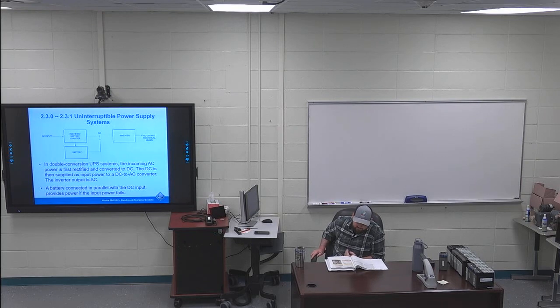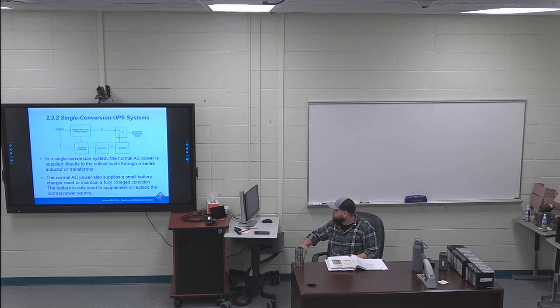The next sentence is a separate highlight. In low power UPS applications, 0.1 kilovolt amps to 20 kVA, the double conversion UPS can have some of the following disadvantages. I just have the lower efficiency. So at these levels, these UPS systems can have a lower efficiency. Going on to 232, the single conversion UPS system, I've got the second sentence highlighted. The normal AC power is supplied directly to the critical loads through a series inductor or transformer.